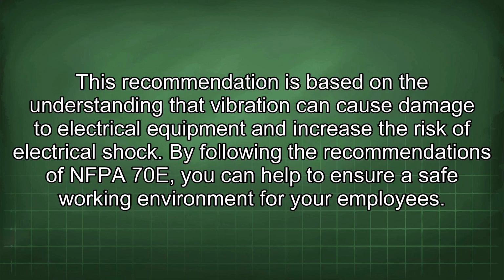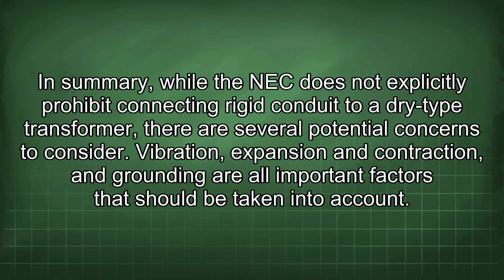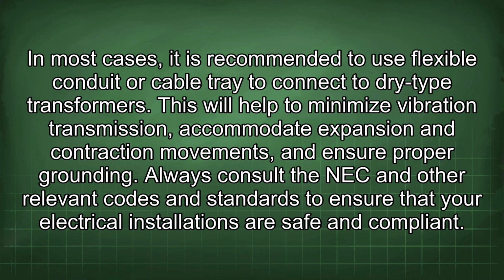By following the recommendations of NFPA 70E, you can help to ensure a safe working environment for your employees. In summary, while the NEC does not explicitly prohibit connecting rigid conduit to a dry-type transformer, there are several potential concerns to consider. Vibration, expansion and contraction, and grounding are all important factors that should be taken into account. In most cases, it is recommended to use flexible conduit or cable tray to connect to dry-type transformers.